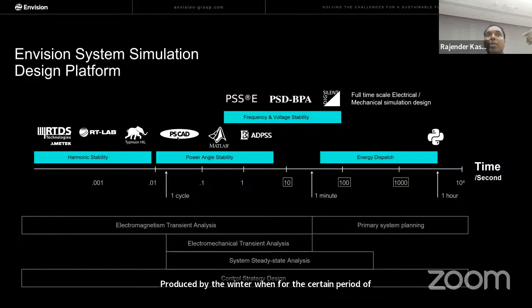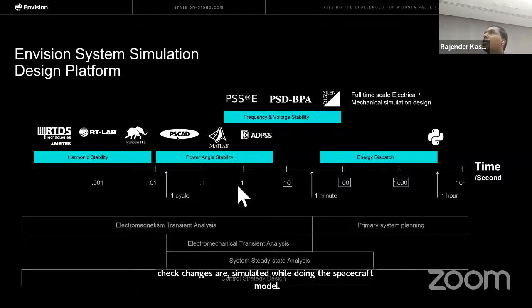So when you do the PSCAD model at the network level, you'll identify how the system is behaving. Based on that, you can design the parameters or the set points within the PCS. Also the parameters on the converter protection level, the balanced and unbalanced faults, the voltage and frequency disturbances, and active and reactive power dispatch commands. These step changes are simulated while doing this PSCAD model. So Envision, we offer that solution.